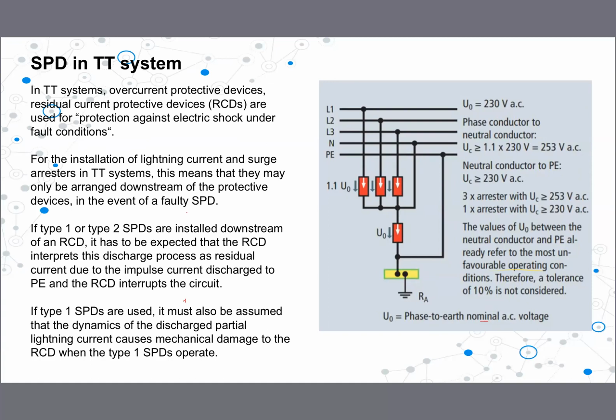And also, when you install type 2 surge protection devices, we install the surge protection device above the RCCB. Otherwise, if there is a fault in the surge protection device, there can be nuisance tripping in the RCCB also, right? When the surge protection device diverts the surge, if we install it below the RCD, the RCD will take it as a residual current difference, right? It will appear on the RCCB as a current difference, and at the time the surge protection device protects against the surge, your RCCB will also be tripped. So it is not a good thing. Therefore, we need to install type 2 surge protectors above the RCCBs, right?